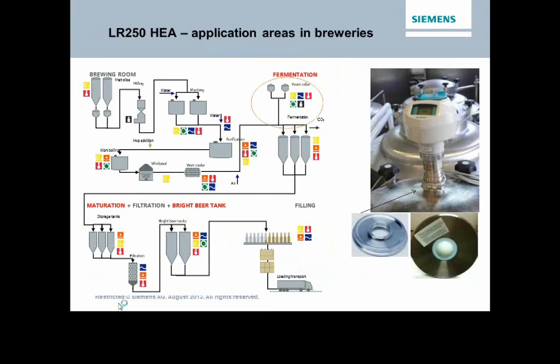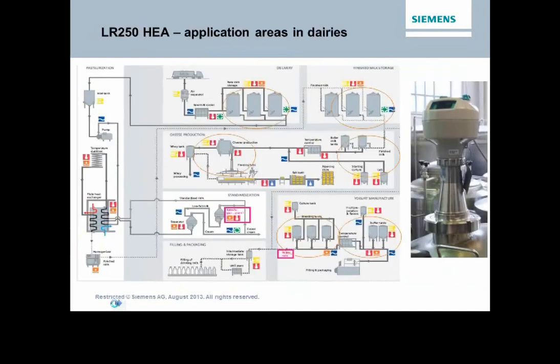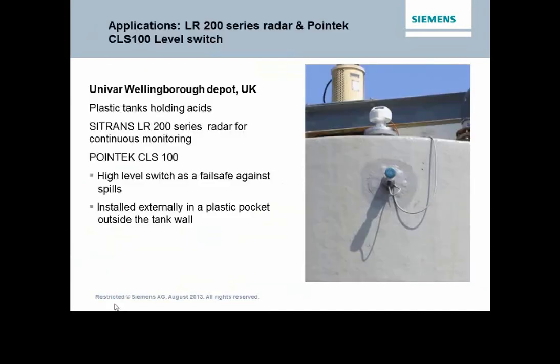When it comes to applications, we actually do have a full applications group. One of my jobs, as an applications engineer, is to review applications and make recommendations. And we have the tools to do that. We talked about earlier using applications. We'll use radar as a continuous level measurement, and then a level switch as a process connection, as good engineering practice for fail-safe control, especially in critical processes. We want to have a high-level switch. In this case, this is an extremely nasty application, and they're actually using a point-level switch as an interstice measurement within a double tank wall. So if there was a leak in that wall, this was going to measure that.